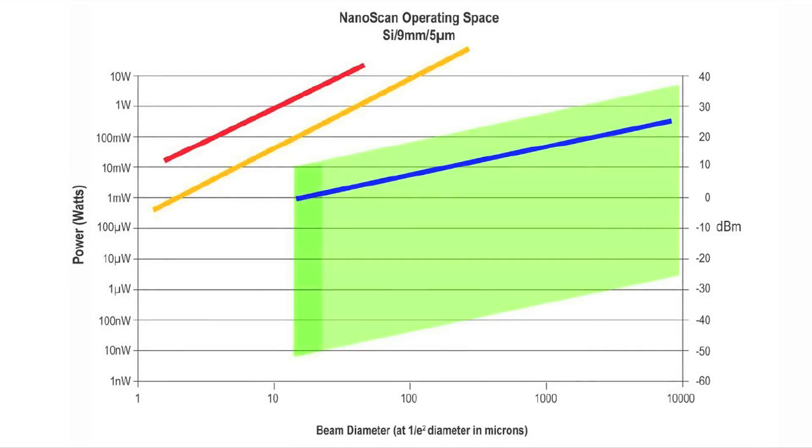In the green box, the left boundary shows the smallest beam size limited to 4 to 5 times the slit width. The right boundary indicates the largest beam width of a 1 over e squared width, which is the aperture size divided by approximately 1.3.